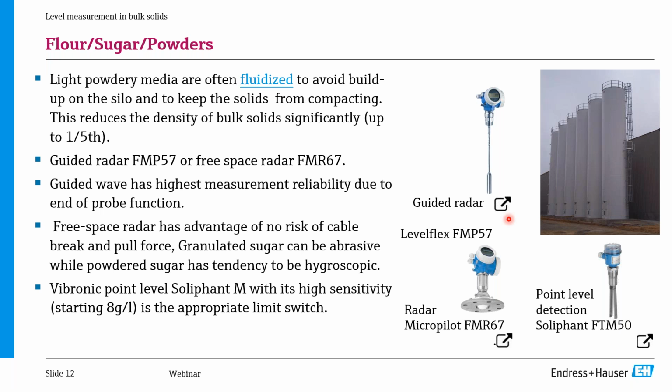technology, because you have to put a rope inside your silo, and this rope is often exposed to mechanical stress. And depending on the conditions, you can also have the risk of a cable break due to the tension caused by the weight of the material.